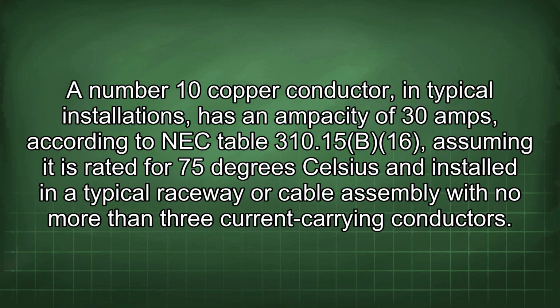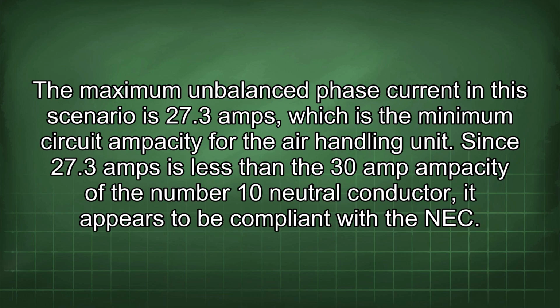A number 10 copper conductor, in typical installations, has an ampacity of 30 amps according to NEC Table 310.15(B)(16), assuming it is rated for 75 degrees Celsius and installed in a typical raceway or cable assembly with no more than 3 current-carrying conductors. The maximum unbalanced phase current in this scenario is 27.3 amps, which is the minimum circuit ampacity for the air handling unit. Since 27.3 amps is less than the 30 amp ampacity of the number 10 neutral conductor, it appears to be compliant with the NEC.